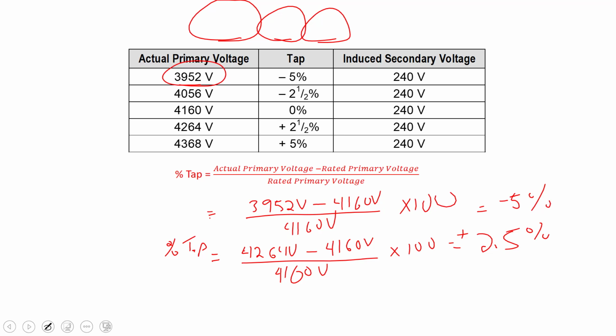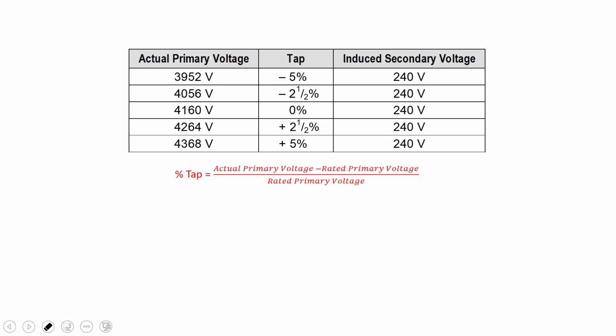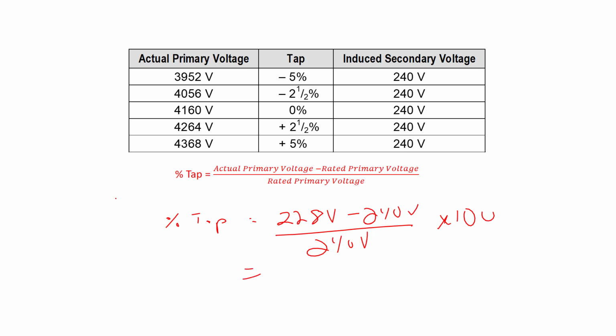Can this be done with secondary voltages? Sure, absolutely. So my rated secondary voltage is supposed to be 240, and let's say that I was only getting, let's say, 230 volts roughly. I'm just kind of throwing a number out there. And if I did this in the field, what would happen, right? So let's go erase all ink on the slide. Let's say that for the percent tap, let's just use it with the secondary voltages. Let's say that the actual secondary voltage was, I don't know, what did we say, 228 before? So 228 volts, right? And I'm going to subtract 240, divide by 240, and times it by 100. Okay, what would that look like? Let's go grab that calculator.